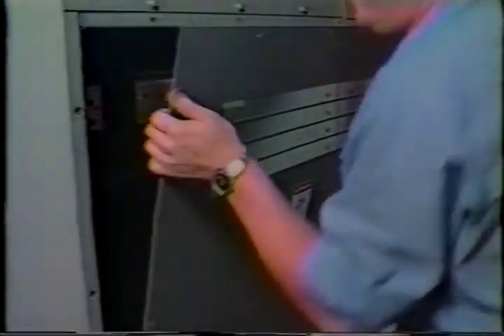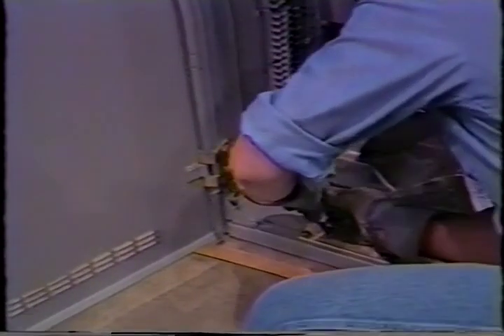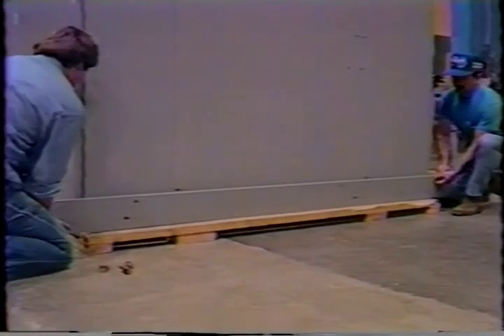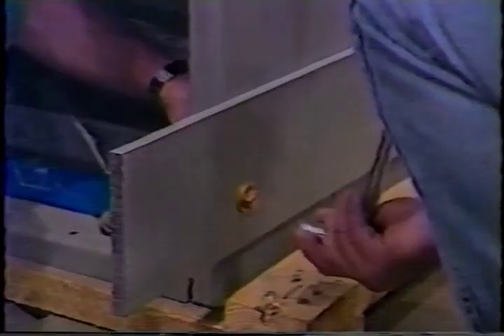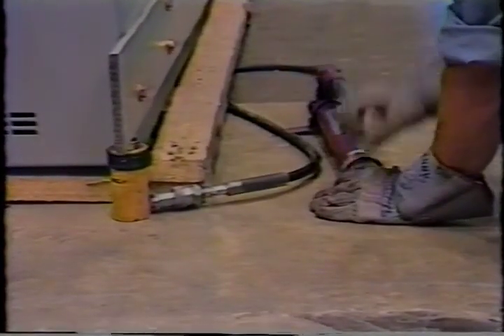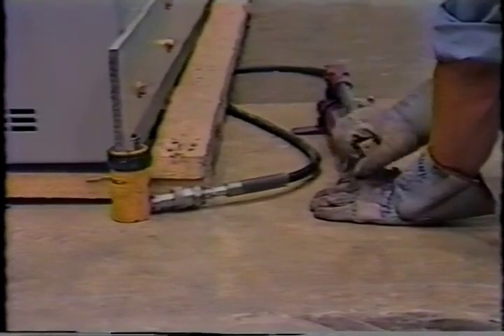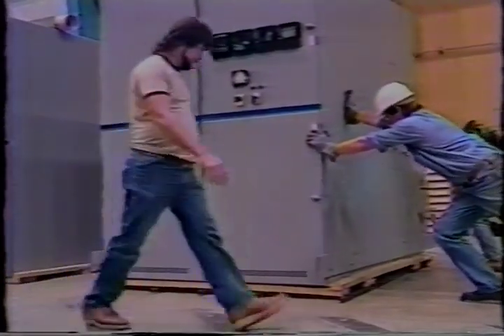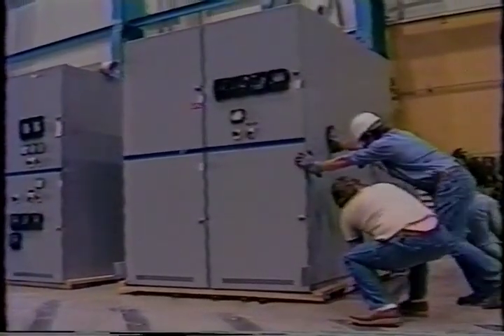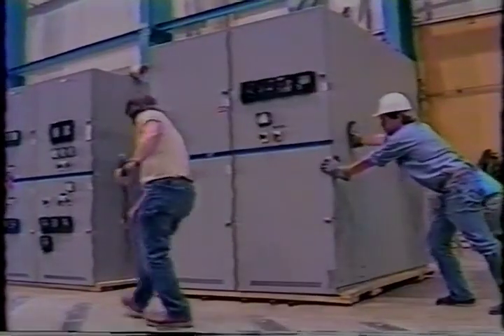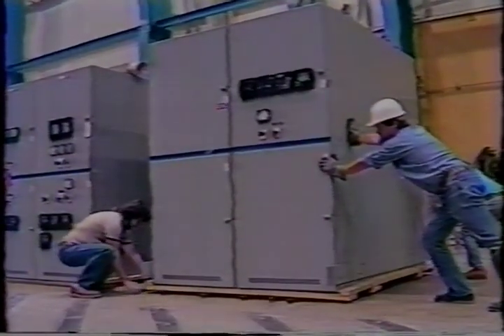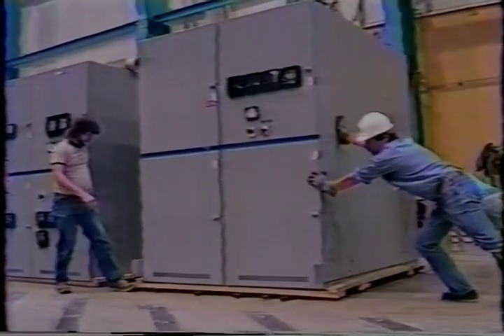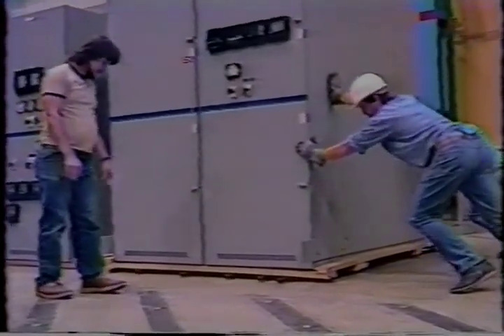First, unbolt and remove rear covers. Remove the snap plugs. Attach the jacking plate. Raise the front and rear, and insert the pipe rollers. Never maneuver the switchgear directly on rollers. Always use the skids to protect the switchgear from being distorted or damaged. The shipping skids are held in place with bolts. Remove the bolts and discard the skids.